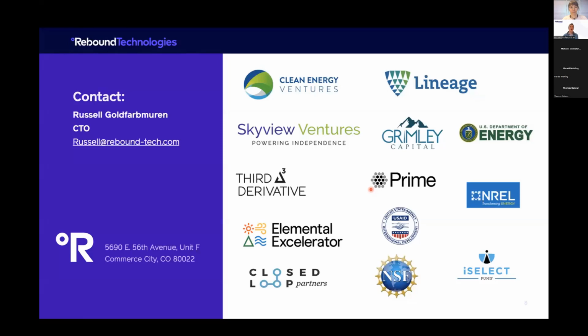The key, though, why other systems don't use potassium acetate is that when you use a liquid desiccant in isolation, you have to have a really high concentration, because you need to get to very low dew points using only your brine. So you need a desiccant like lithium chloride that you can concentrate quite high. We don't have that constraint because we're doing simultaneous cooling and desiccation, so our brine is quite low concentration from a liquid desiccant standpoint, and we don't need those extremely high activities that lithium chloride requires.